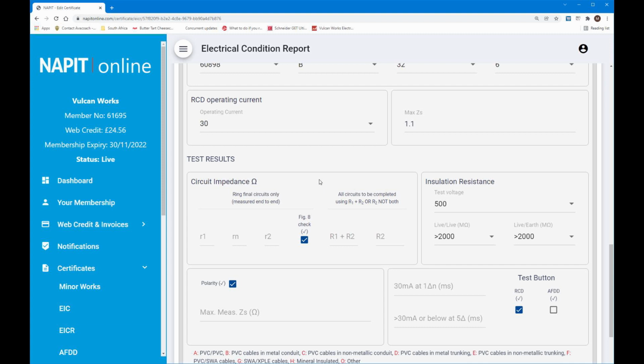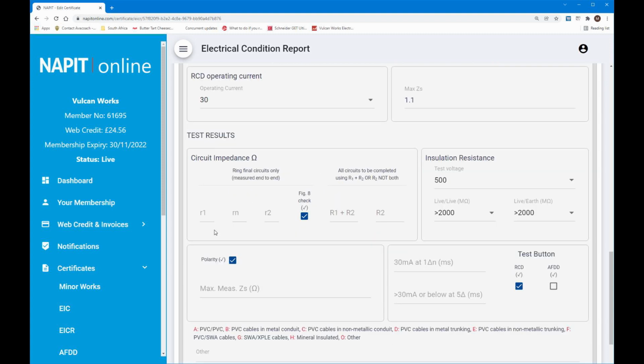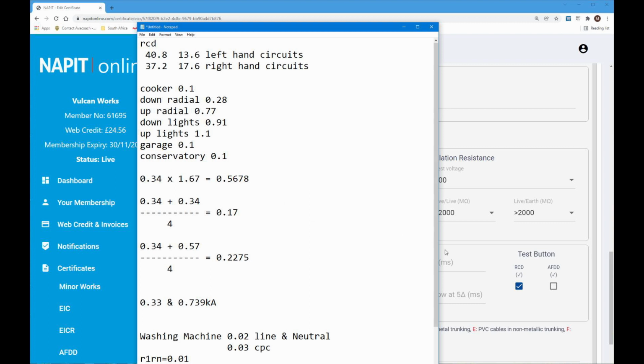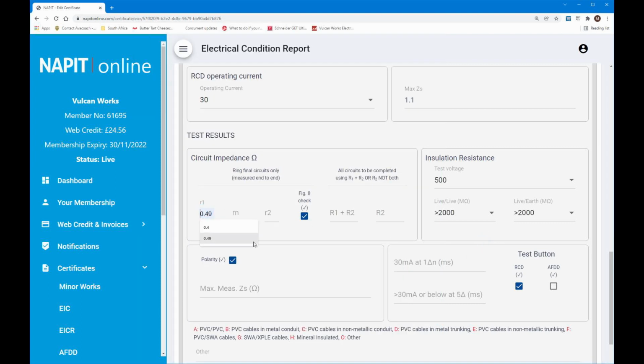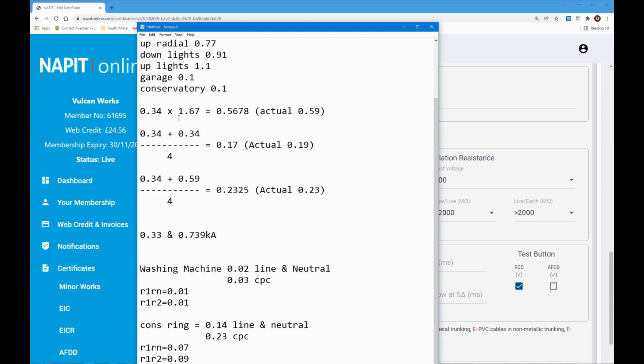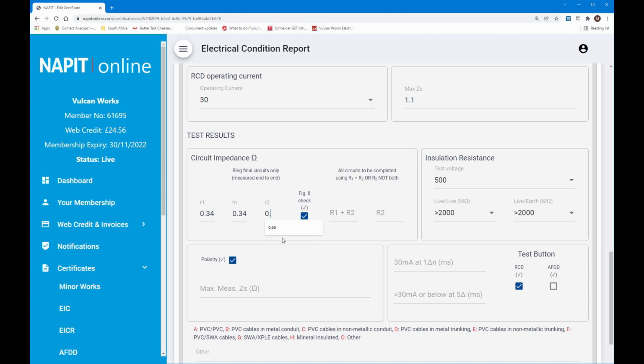So now we come down to this. Let's have a look. In the kitchen, I took a reading of the R1, which is connecting the line to line on both ends of the ring, and that came out at 0.34, and it came out 0.34 for both the R1 and the RN. So the R2 reading. Let's go back to my notepad, and you'll see that I have multiplied the 0.34 by 1.67 because of the CPC being 1.5, and that gave me a calculated value of 0.56. And if you saw in the video, the actual value was 0.59, which is absolutely fine, well within tolerance. So let's put that value in, 0.59.